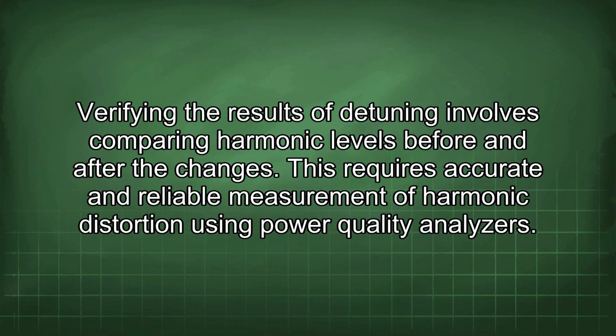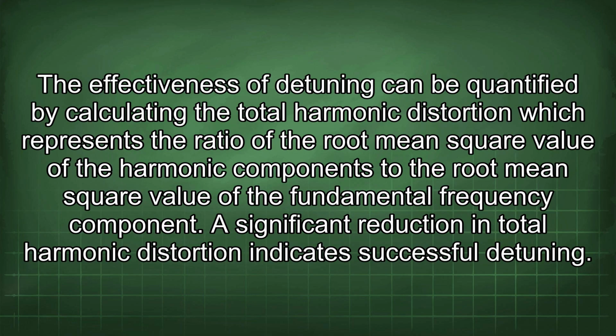Verifying the results of detuning involves comparing harmonic levels before and after the changes. This requires accurate and reliable measurement of harmonic distortion using power quality analyzers. The effectiveness of detuning can be quantified by calculating the total harmonic distortion, which represents the ratio of the root mean square value of the harmonic components to the root mean square value of the fundamental frequency component. A significant reduction in total harmonic distortion indicates successful detuning.